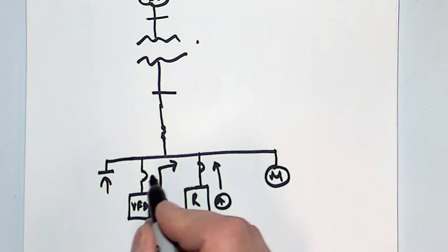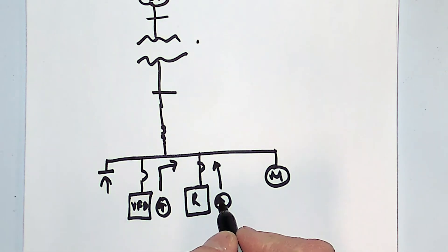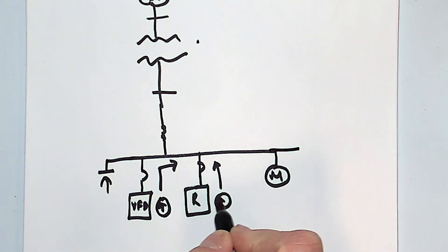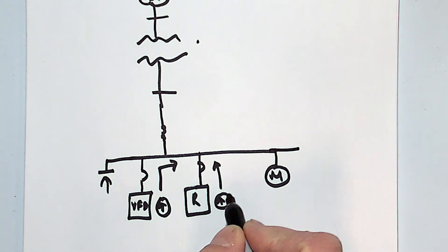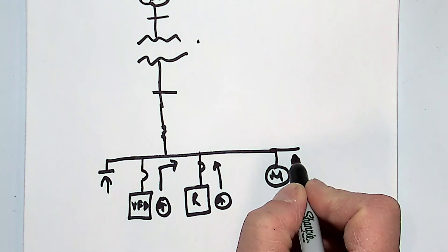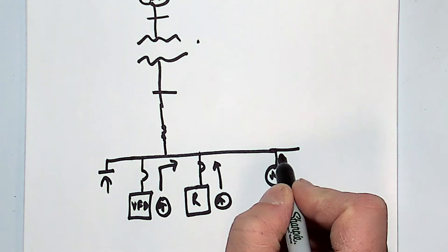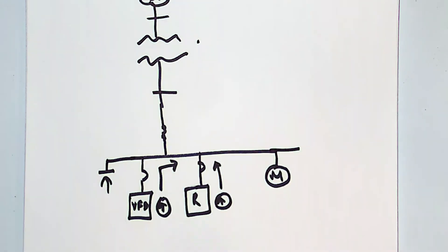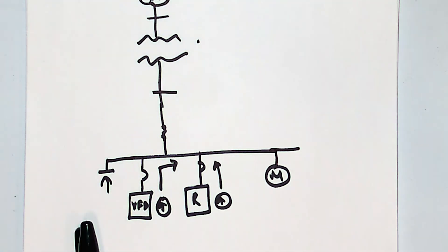It's a very simple system. What we do is we look for current distortion coming out of the drives or the loads, and we look for voltage distortion on the common buses that are going to affect the power system and perhaps put us over the limits of IEEE 519.